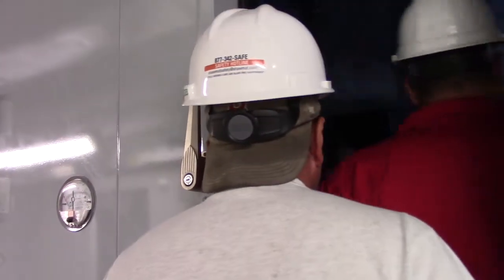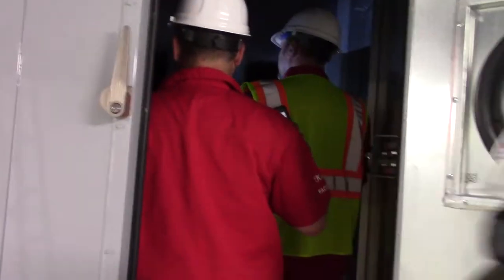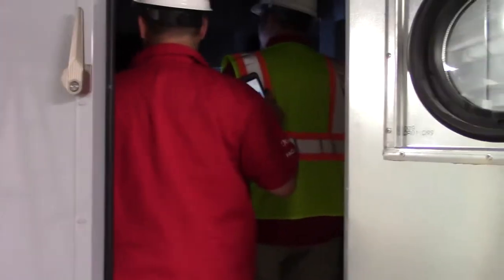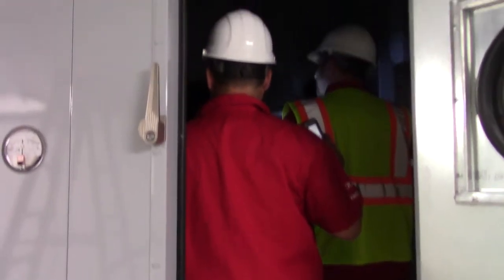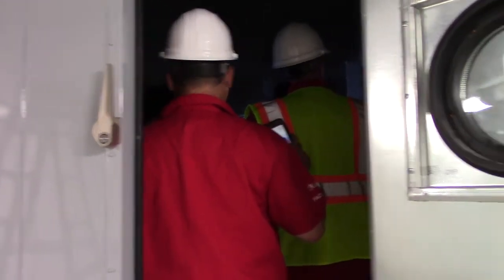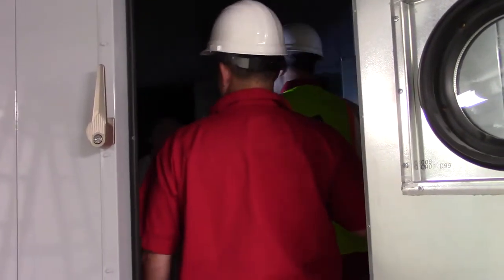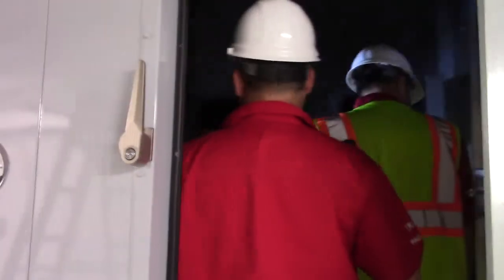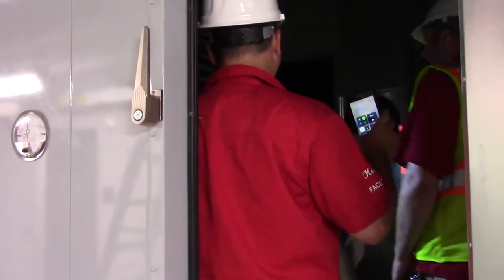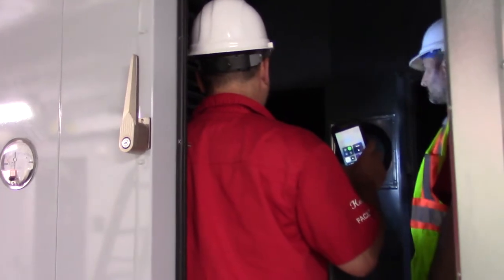You've got the heat wheel right here. If you have to clean the heat wheel, we don't want any solution on it or anything like that. Just hit it gently with nitrogen, no more than 100 psi, and then put a shop vac on the other side, and try to suck up all the dust that blows out of it. If you change the filters regularly, you shouldn't really have to clean that out.